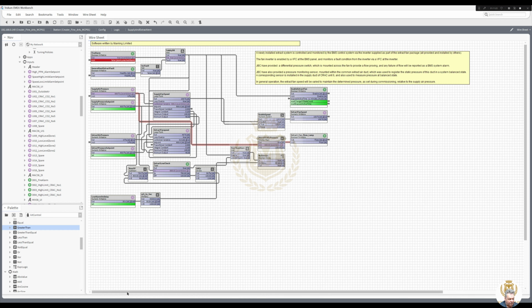So let's get a scheduler. We could use a trigger, but I'm just going to use a scheduler. Boolean. And we'll put in that as flush system Legionella. We'll do it on a working day. No, this can be changed, of course. So that's 12 to 12:30. We only want 2 minutes every Sunday morning.